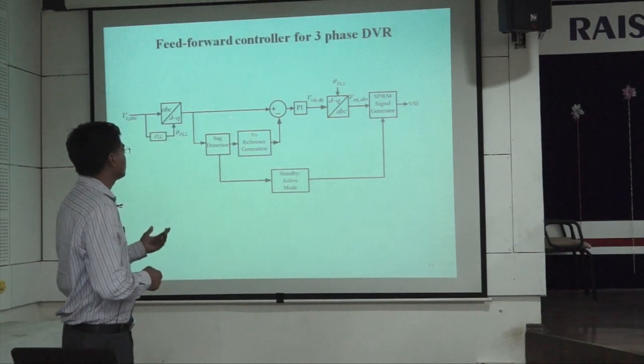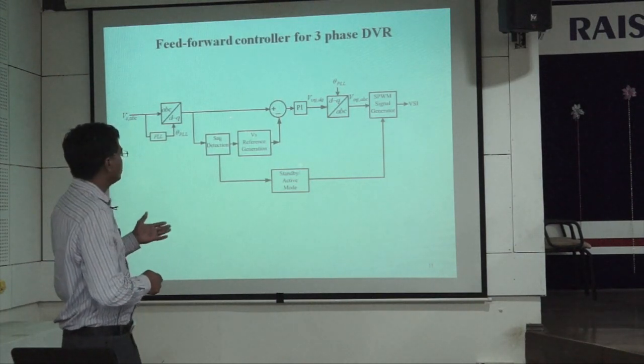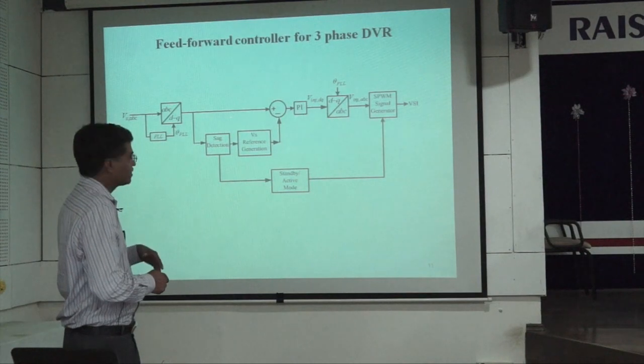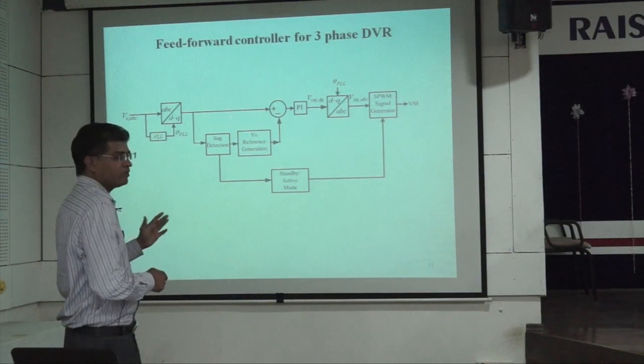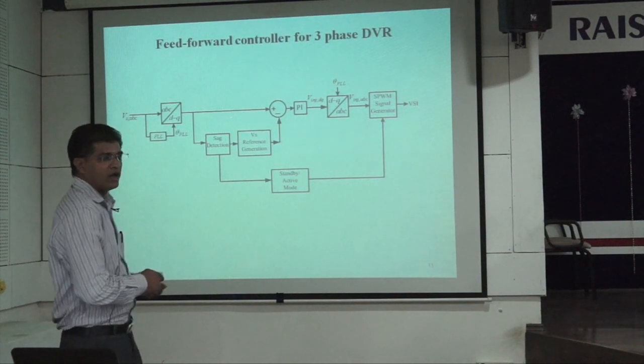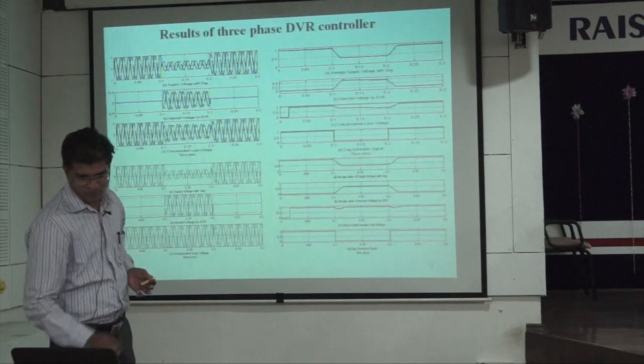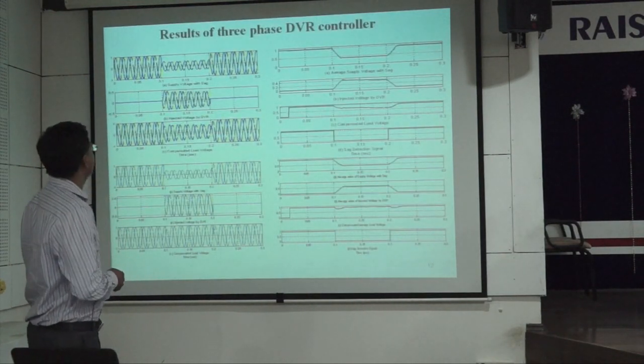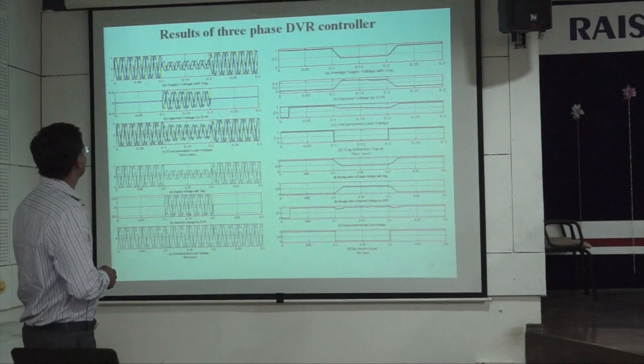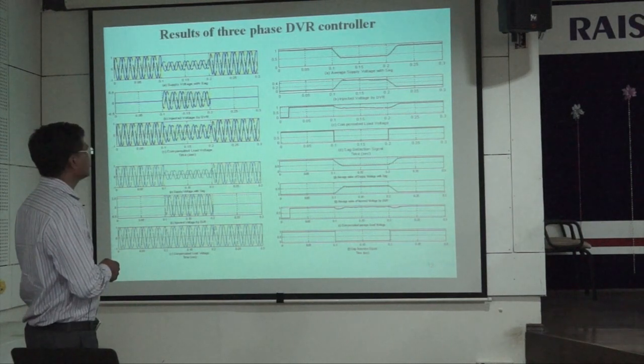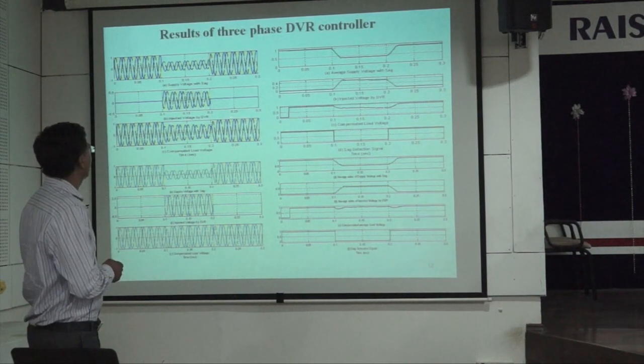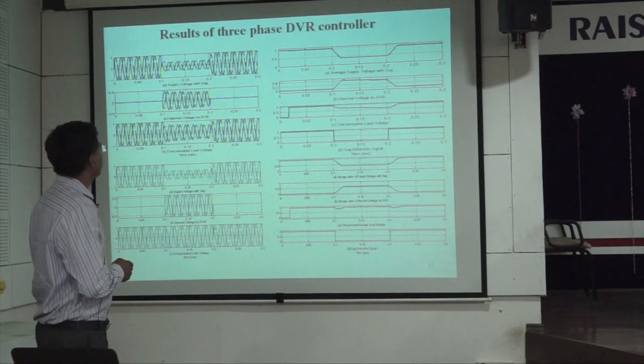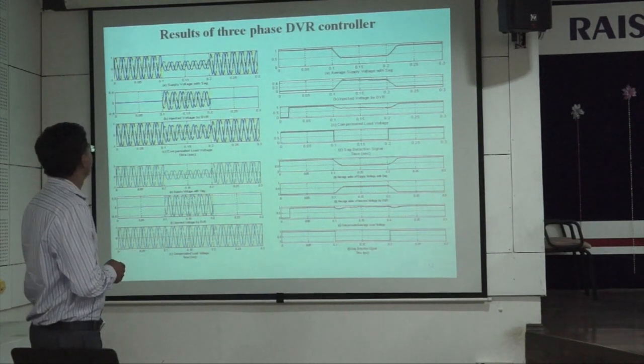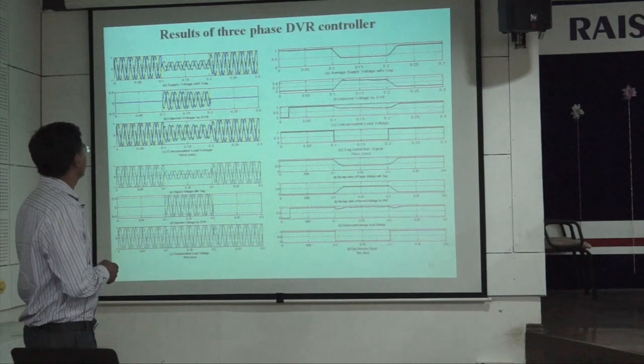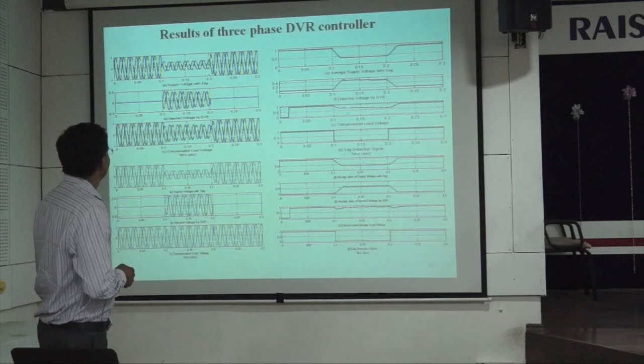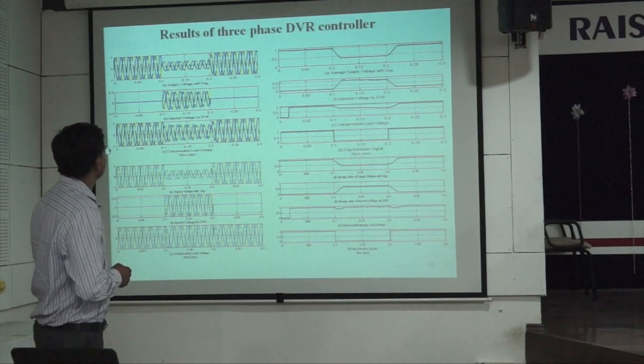During the standby mode, the energy storage device is getting charged, and whenever there is a sag, it will be converted from standby to active. These are the results of the three-phase DVR, where the sag is initiated at 0.1 second. It will remain for around 7 cycles up to 0.2 second, and this is the injected voltage by the controller through the transformer.